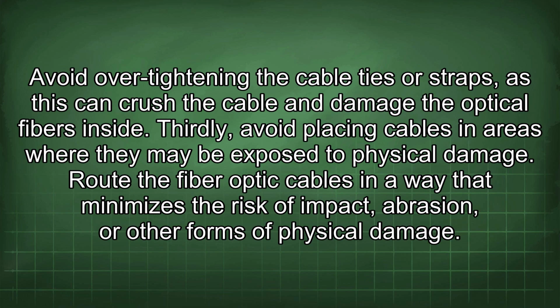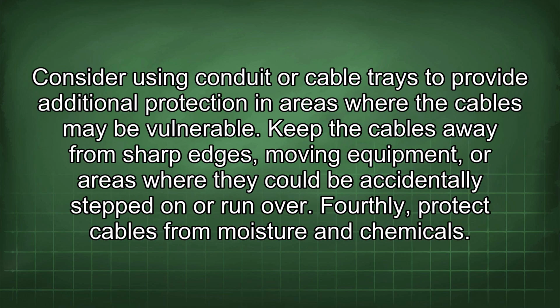Thirdly, avoid placing cables in areas where they may be exposed to physical damage. Route the fiber optic cables in a way that minimizes the risk of impact, abrasion, or other forms of physical damage. Consider using conduit or cable trays to provide additional protection in areas where the cables may be vulnerable. Keep the cables away from sharp edges, moving equipment, or areas where they could be accidentally stepped on or run over.